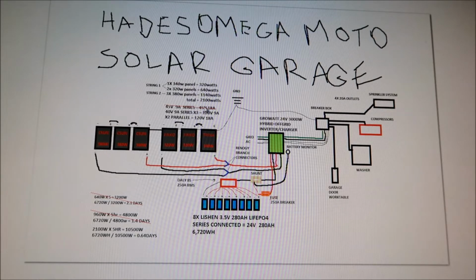This tells you how much power the strings make up. String 1 is 320 watts plus 640 watts, which is about 940 watts, pretty much a kilowatt. Does it make that much in a day? Yes and no - it depends on how much sunlight we got. So there it is, we've got these wired up in series, and then it connects to the inverter.